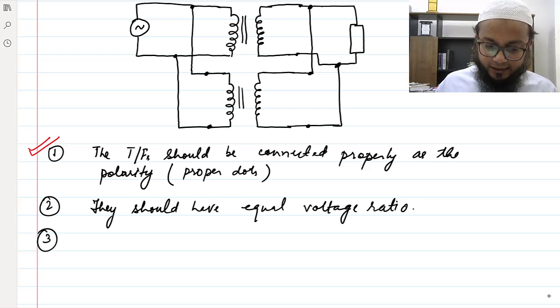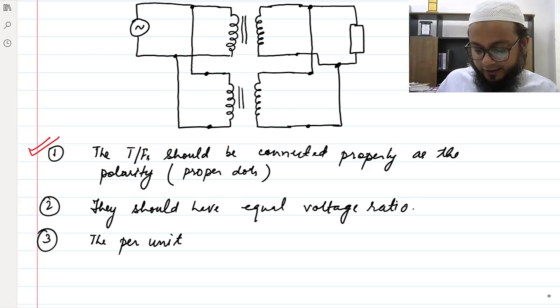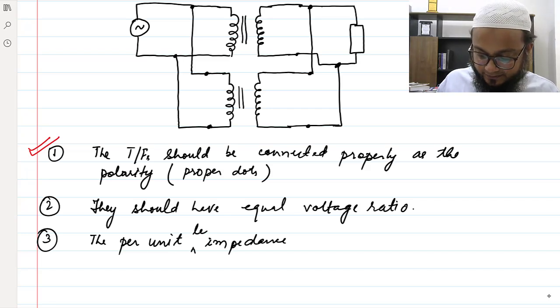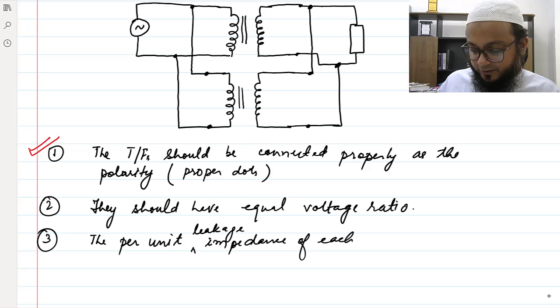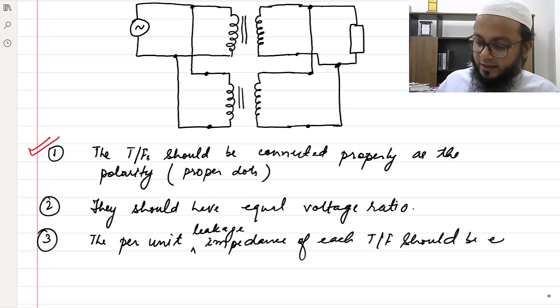The third condition is the per unit impedance, sorry, the leakage impedance, the per unit leakage impedance of each transformer should be equal.